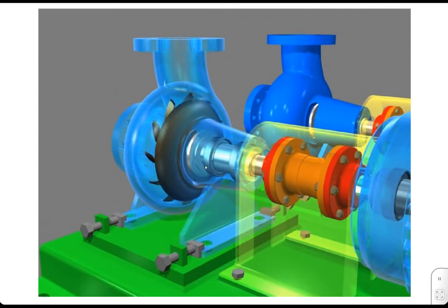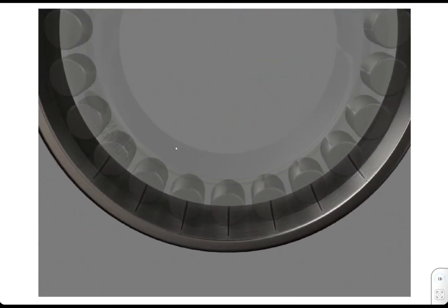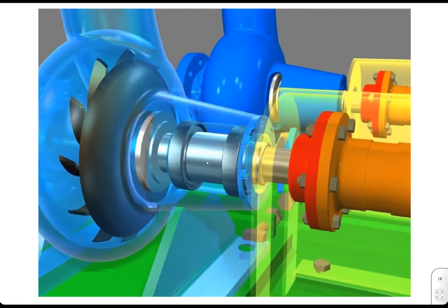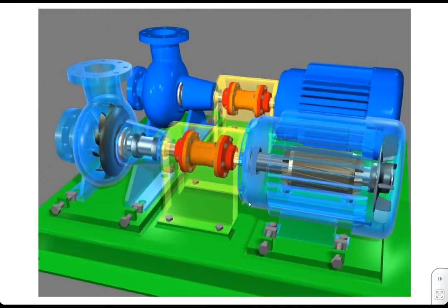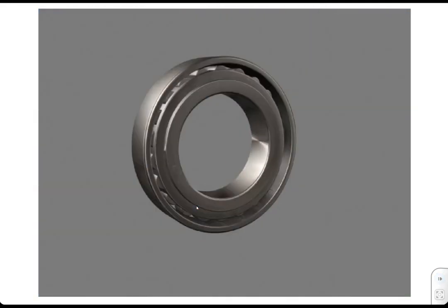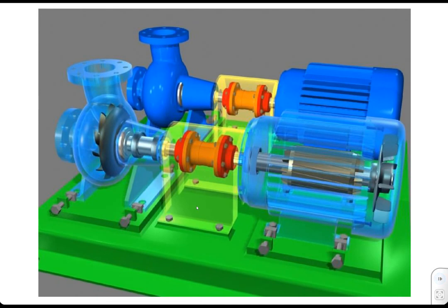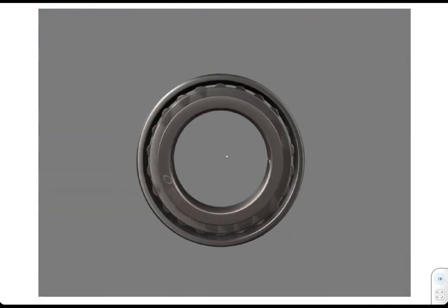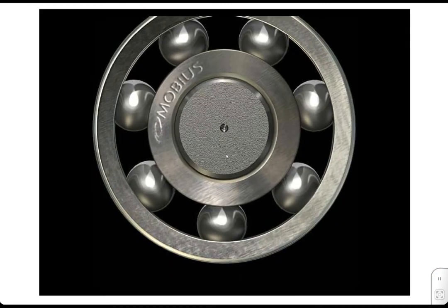When you've got a unit in standby mode, its mate next to it is vibrating because it's operating, and therefore this machine will also sit there and vibrate, but because the rolling elements aren't turning, it creates these indentations, and that happens when bearings are being transported. It happens when bearings are sitting on the shelf as well. So there are ways around all these problems. If we operated this machine more frequently, or if we mechanically isolated the machines, we can solve these problems. No worries about that.